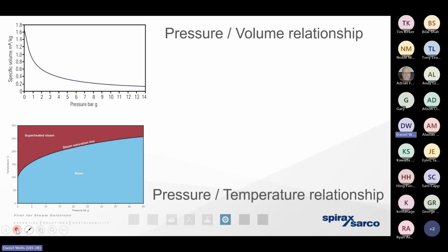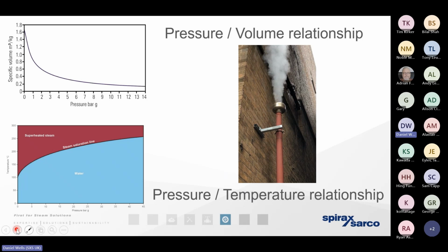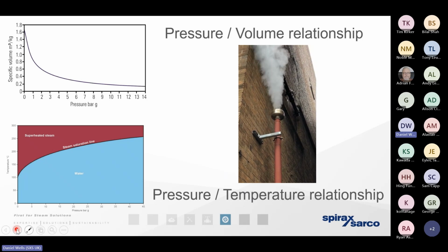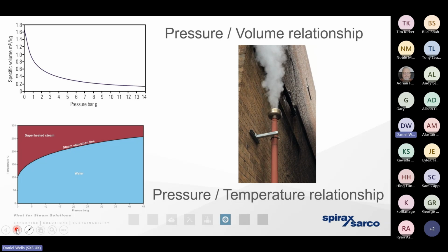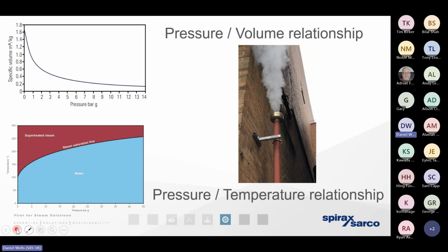Now, in previous presentations that we went through, we mentioned the reason for those steam vents. For the simple reason that if one of those steam traps were to fail, we're going to have high pressure, small volume steam depressurizing and expanding. But we're also going to have high temperature, high pressure condensate depressurizing. And of course, when that happens, a certain percentage is going to want to boil off and expand and change state to steam again. So of course, we're going to have to vent that expansion away so we don't get damage to the infrastructure. The problem is it's a necessary evil.